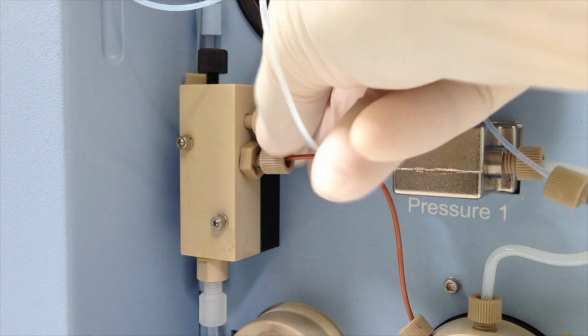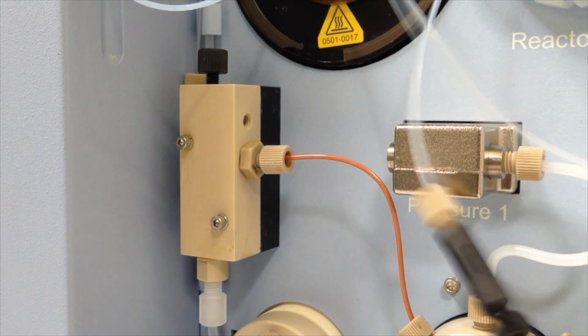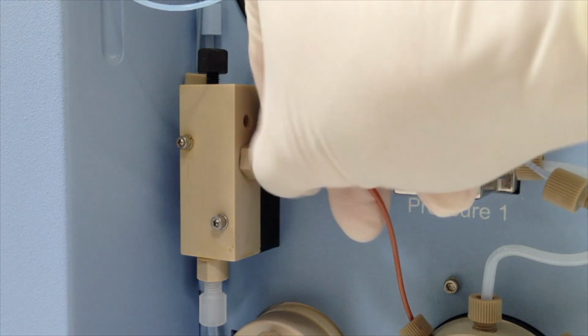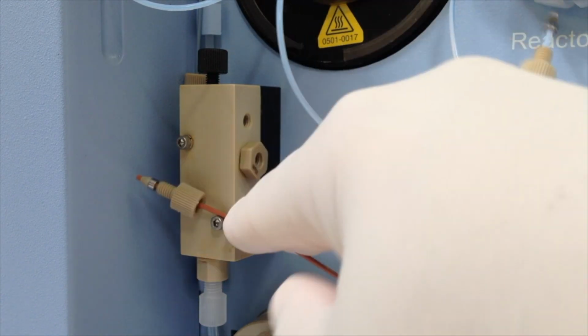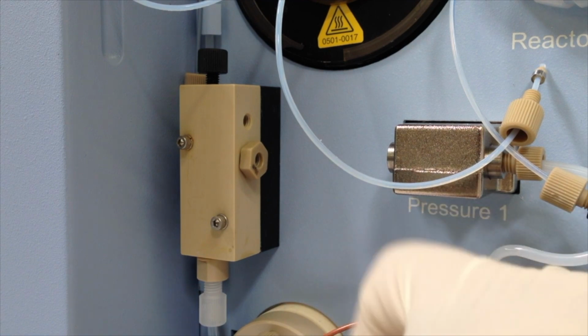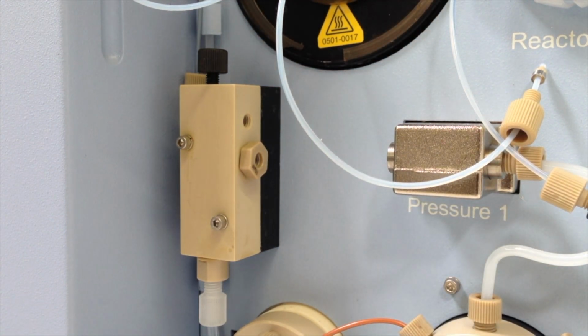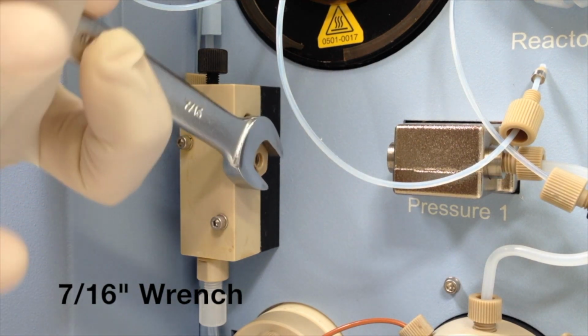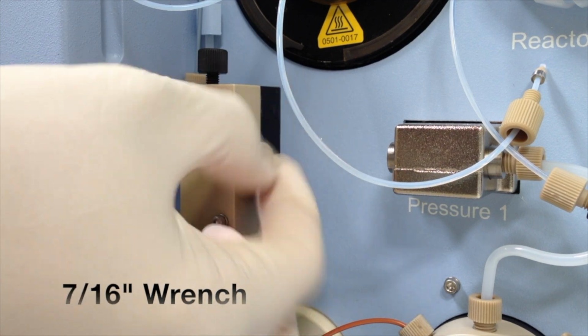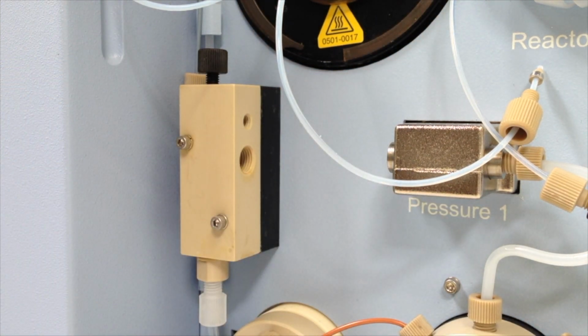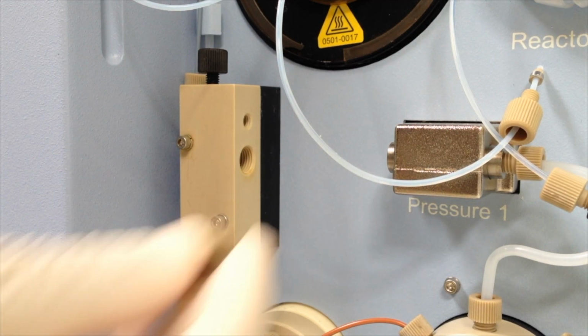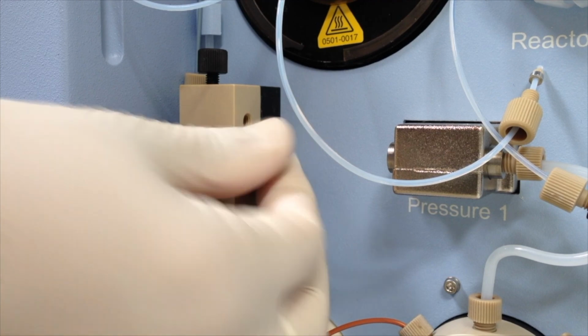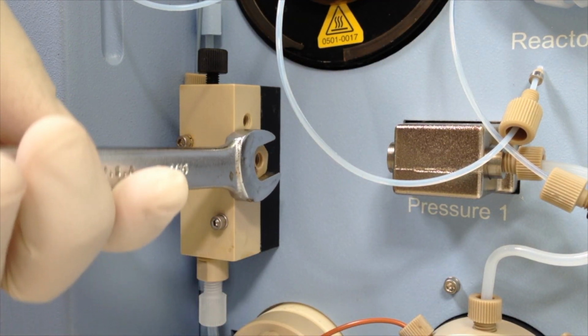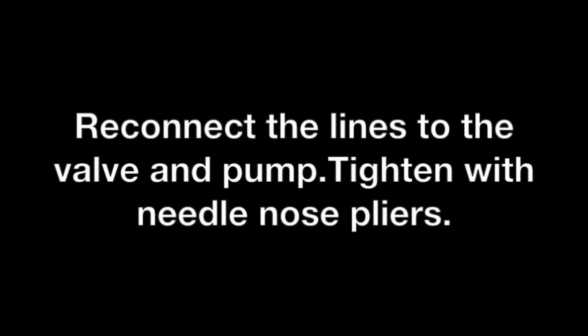Remove the tubing connections to the mixing tees so you can replace the 10 micron filters. Use a 7/16 inch wrench to remove the 10 micron filter from the mixing tee. Replace the filter with a new one by screwing in the new filter finger tight, and then use the 7/16 inch wrench to tighten a quarter turn. Reconnect the lines to the valve and pump. Tighten with needle nose pliers.